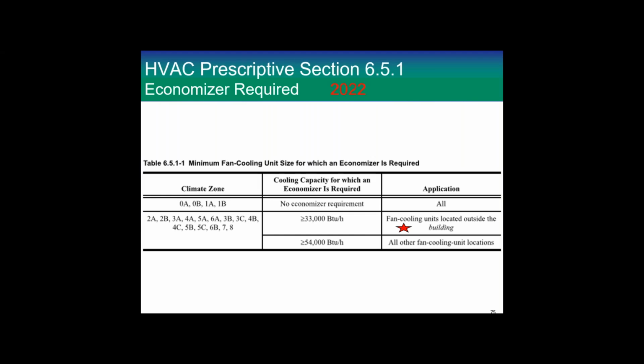So for the prescriptive section, this is where economizers are required. In the warmest climate zones, 0A, 0B, 1A, and 1B, that's the hot, humid and hot, dry, no economizers are required. That's because the air we're going to bring in is most of the time not usable, so we don't require it because of the paybacks. Everything's based on payback. Now, in all the other climate zones, we require those economizers.